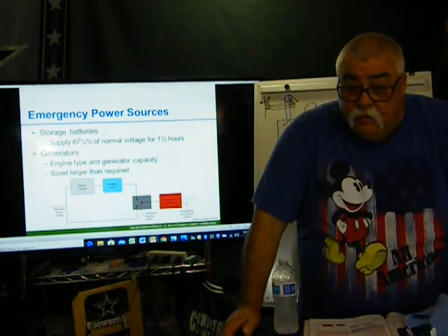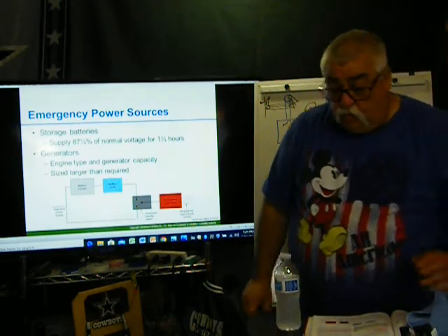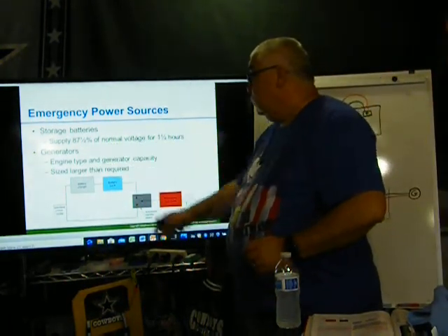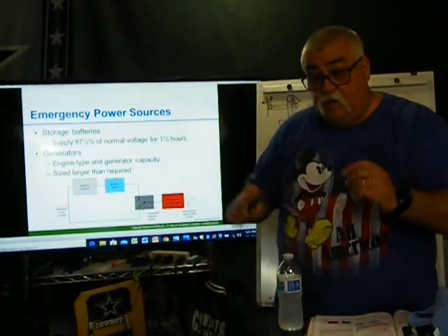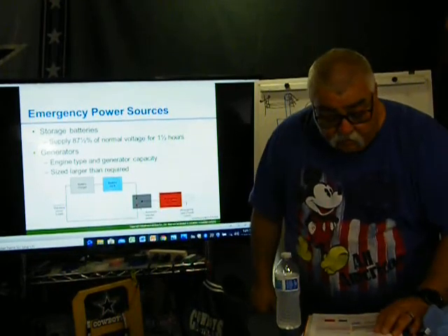So you have storage batteries. When you have storage batteries, they've got to supply 87.5% of normal voltage for 1.5 hours. And we'll get into sizing and all of this. I'll send it as a separate assignment.